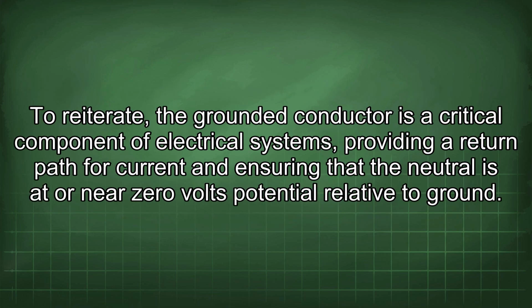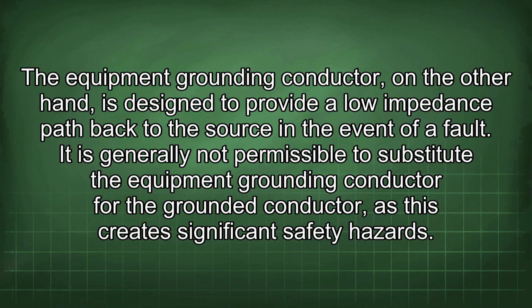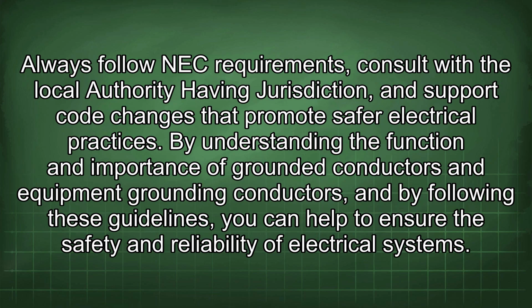To reiterate, the grounded conductor is a critical component of electrical systems, providing a return path for current and ensuring that the neutral is at or near 0 volts potential relative to ground. The equipment grounding conductor, on the other hand, is designed to provide a low impedance path back to the source in the event of a fault. It is generally not permissible to substitute the equipment grounding conductor for the grounded conductor, as this creates significant safety hazards. Always follow NEC requirements, consult with the local authority having jurisdiction, and support code changes that promote safer electrical practices. By understanding the function and importance of grounded conductors and equipment grounding conductors, and by following these guidelines, you can help to ensure the safety and reliability of electrical systems.